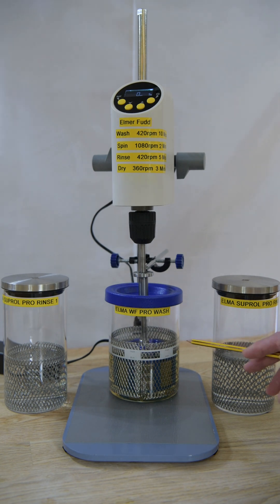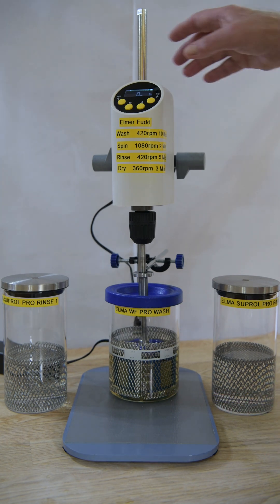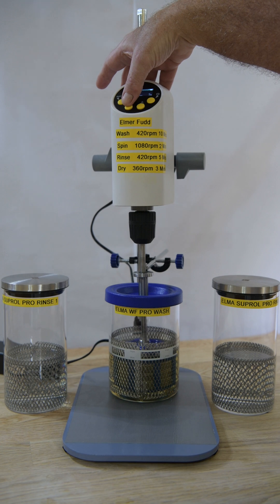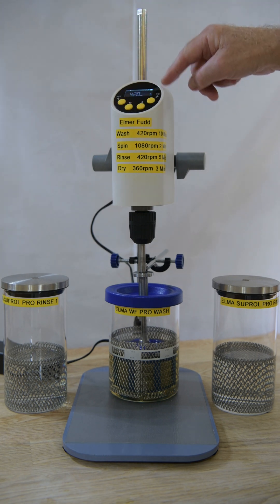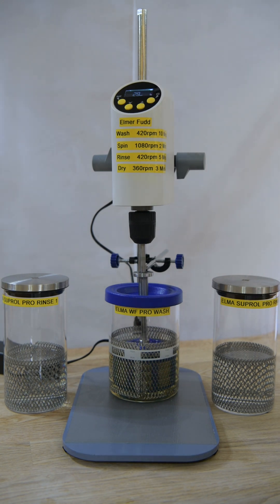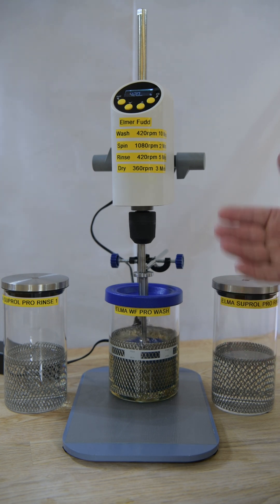At the moment I've got the basket set up just immersed in washing solution. This is Elma WF Pro Wash. I can actually set the spin speed to 420, so I'll do that. We'll set it for a minute for demonstration purposes. And if I press start, it'll gradually ramp up, giving a readout of the revs per minute at the top here. It'll ramp up to 420.